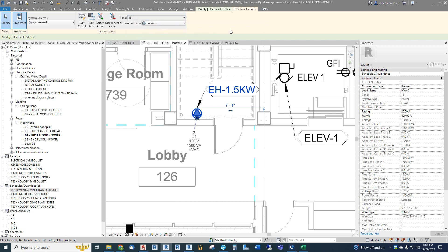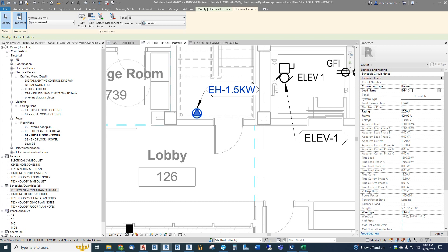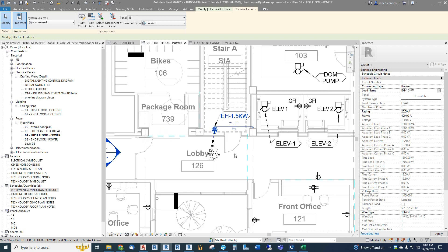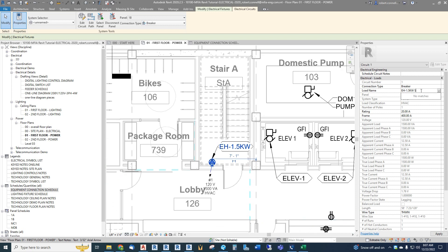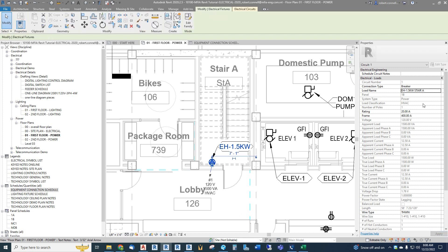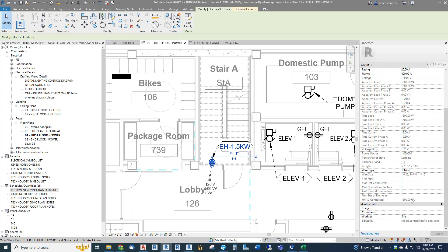It's a breaker, and over on the right it assigned it to circuit 1 of panel 1B. It brings in a load name — typically the load type or room number. We want to label this as 'EH 1.5 kW,' and then it's located in Stair A. Enter and apply it. Make sure it sticks — 20 amp sounds right, we can change it later. Don't worry about the frame or anything else. That's all we have to do — escape out of there.